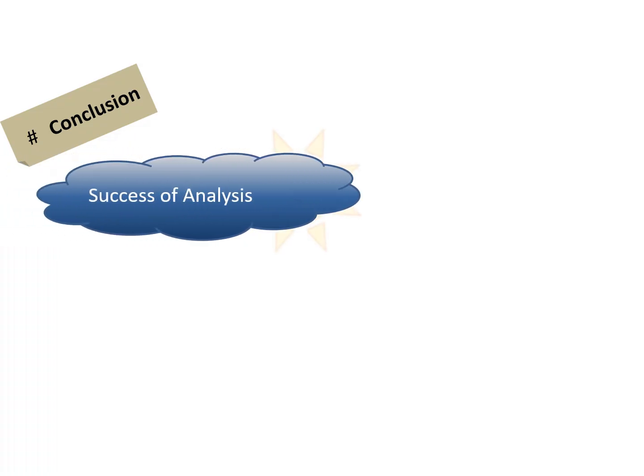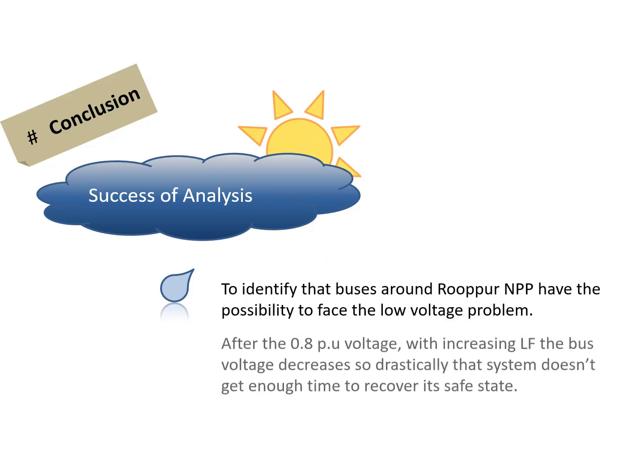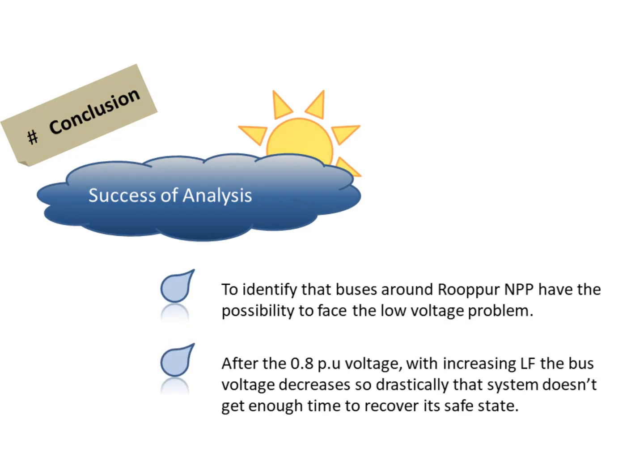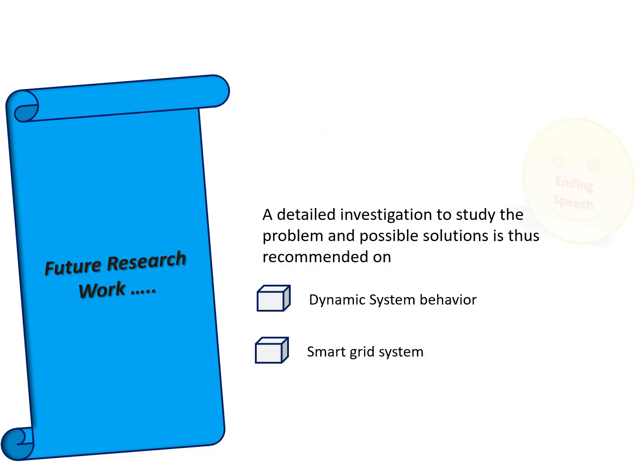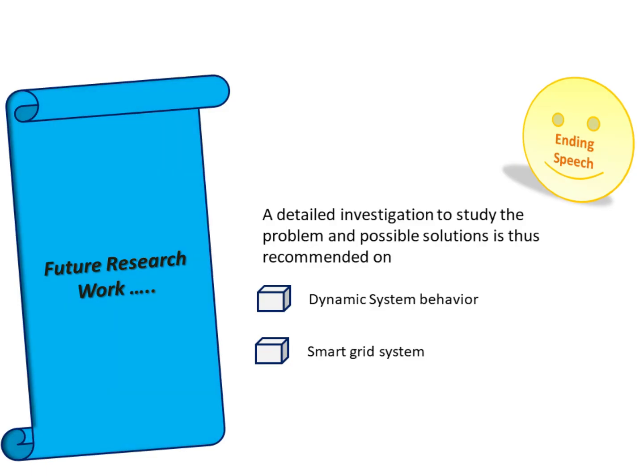Our analysis confirms that buses near Rooppur NPP are at risk of low voltage. Beyond 0.8 per unit, increasing load factor causes rapid voltage decline, leaving insufficient time for system recovery. This poses a real threat to NPP operational safety. We recommend further studies on dynamic system behavior and smart grid solutions to mitigate low-voltage risks. This could include real-time monitoring, adaptive protection schemes, and enhanced reactive power support.